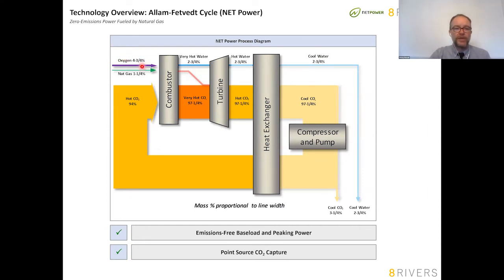The amount of oxygen coming in is only around just under 5% of the mass flowing through the turbine - this is the new oxygen being introduced into the system. The amount of natural gas is about 1.25% of the mass entering the combustor. The majority of it is hot CO2 - 94% of what's entering the combustor is hot recycled CO2. That's what we mean by these being very heavily recuperated and recycled systems.